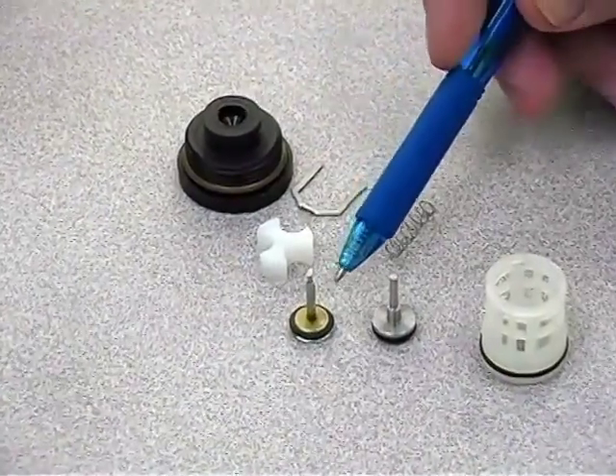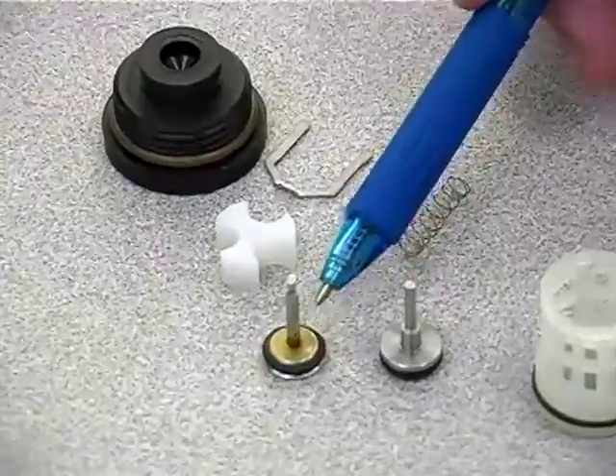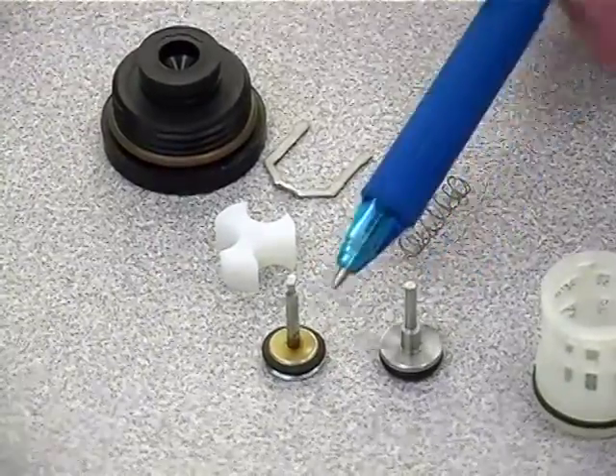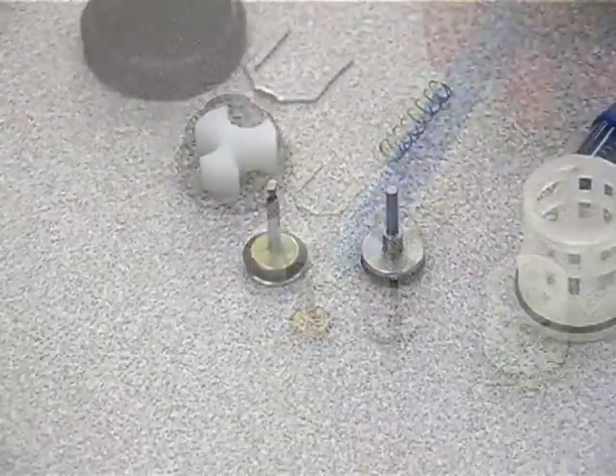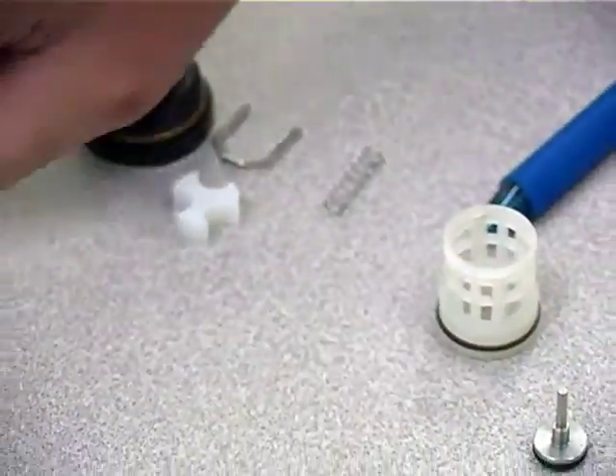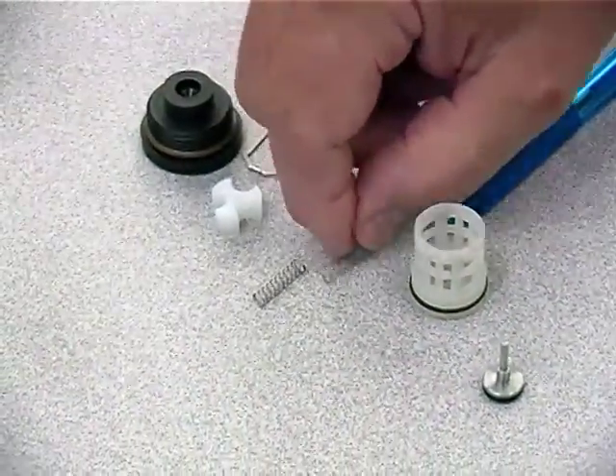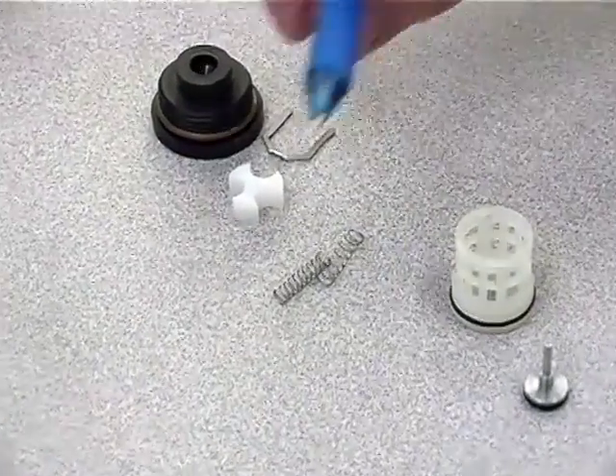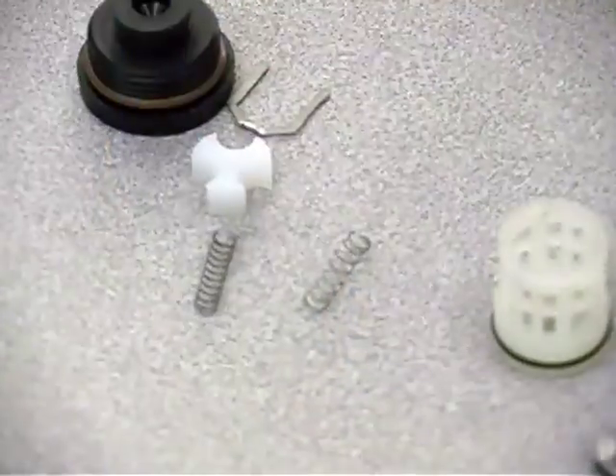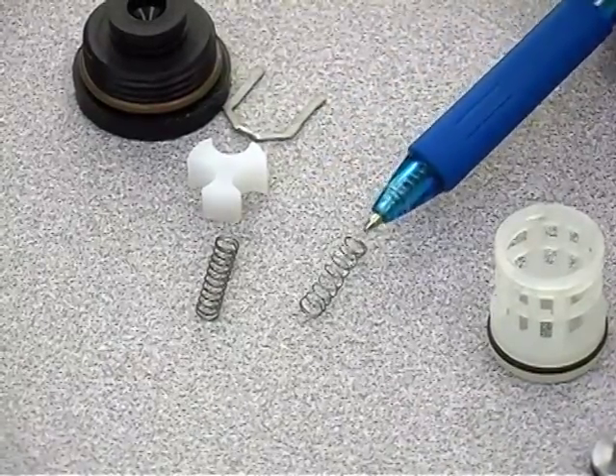If you take a look at the difference between the two poppets, you can see the difference here. This is the intake, this is the discharge. So they're different, but the O-ring will fit the same. And I want to make one other comparison when you're taking these apart. The spring for the intake is wound much tighter than that of the discharge. They are different. That's why I always tell everybody, do them one at a time so you don't get the parts mixed up.